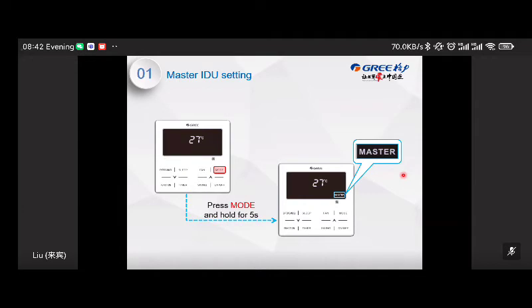So in order to avoid these kinds of mode conflicts, there is a function. We call it master. If you set the master indoor unit, that means the operation mode on this indoor unit will be the priority. If this master indoor unit runs cooling, the others should follow it. If this master runs heating, the others should be heating. It cannot change to the mode conflict status. And when you set the master indoor unit, press this button, mode, for 5 seconds, then this icon will be on. This means the setting is successful.